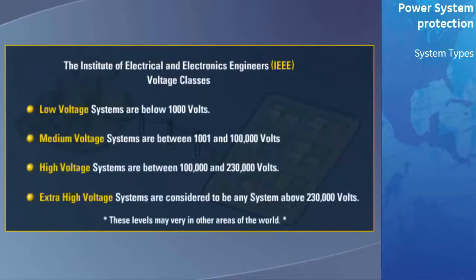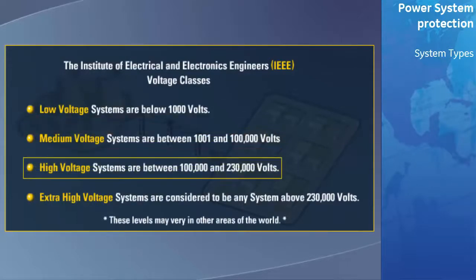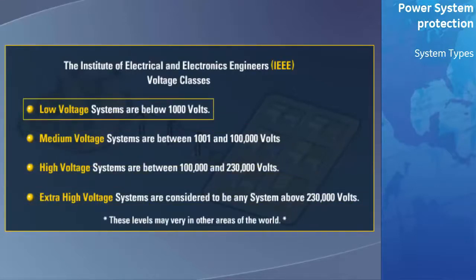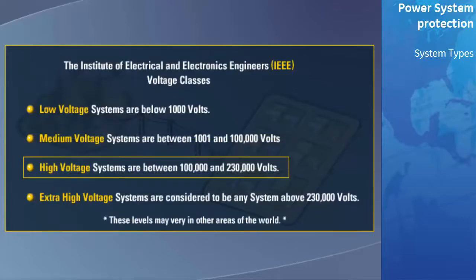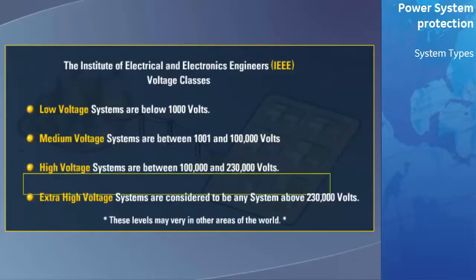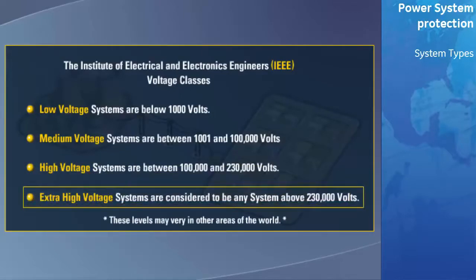The Institute of Electrical and Electronics Engineers, sometimes referred to as the IEEE, have divided voltage systems into low, medium, high voltage, and extra high classes. Low voltage systems are below 1,000 volts. Medium voltage systems are between 1,001 and 100,000 volts. High voltage systems are between 100,000 and 230,000 volts. And extra high voltage systems are considered to be any system above 230,000 volts. The voltage levels may vary in different parts of the world, but the names of the classes for the most part remain consistent.